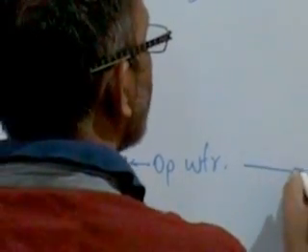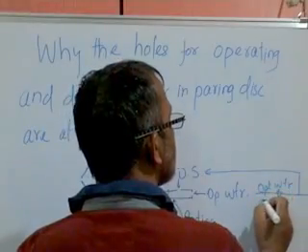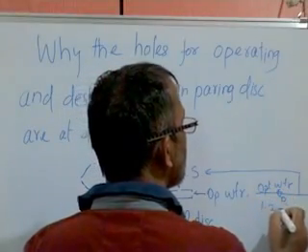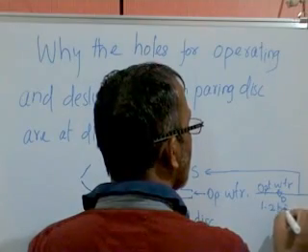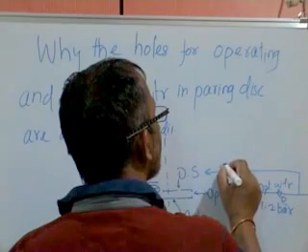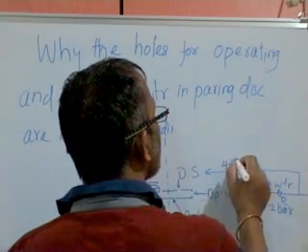That is why for operating water there is a reducer on the water supply from the ship's hydrophore tank. For the desludging water, it is direct. Operating water may be about 1 to 2 bar, and for the desludging water, it is directly 4 to 6 bar.